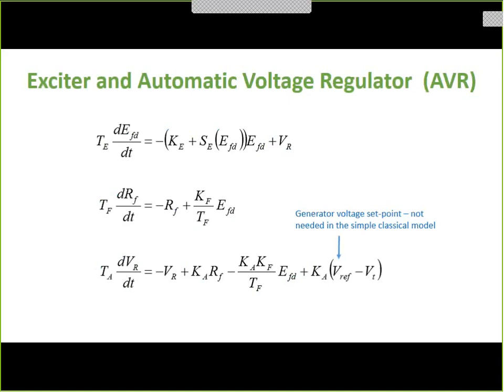Automatic voltage regulation is the next control. I'm not going to go through it. It controls the voltage by changing the exciter voltage, EFD, the top one there. The error signal is determined here. VREF minus VT looks at the error, then amplifies it by KA, feeds it into a control system, which eventually opens up EFD or closes it, depending on whether you want to go up or down.